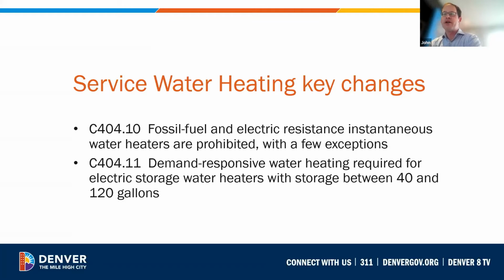A major change to the Denver Energy Code restricts the use of fossil fuel-based water heaters and electric resistance water heaters. The code limits electric storage water heaters to those with a rated tank volume no greater than 20 gallons. This promotes the use of heat pump water heaters, particularly in new construction. The code does provide allowance for electric heat in recirculation loops for larger systems and allows point-of-use heaters when installed within 10 feet of their associated fixtures.